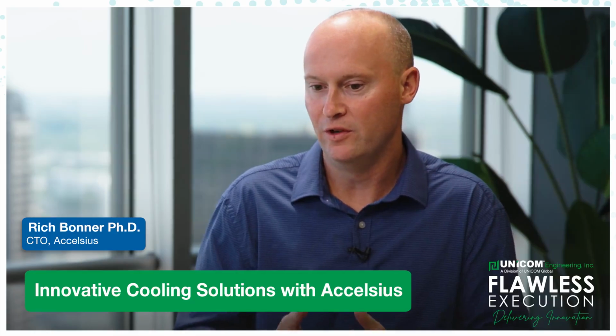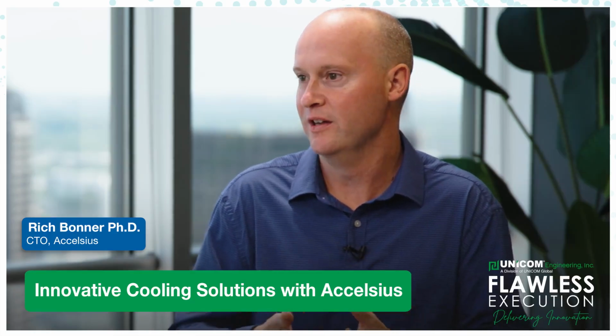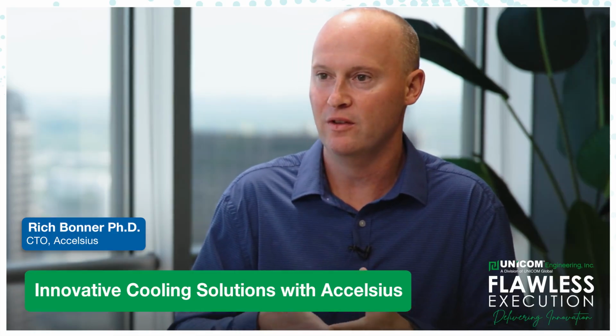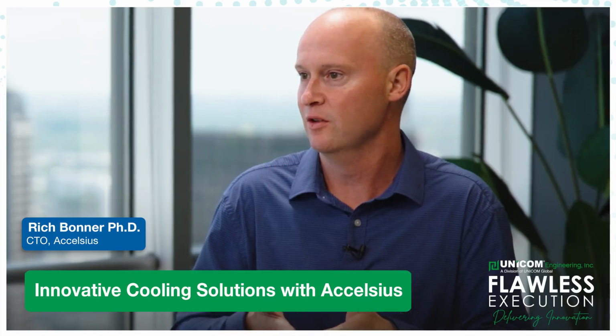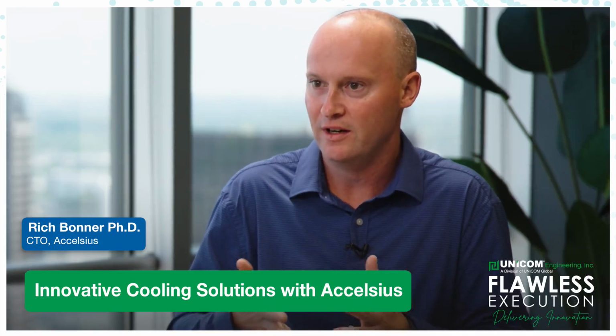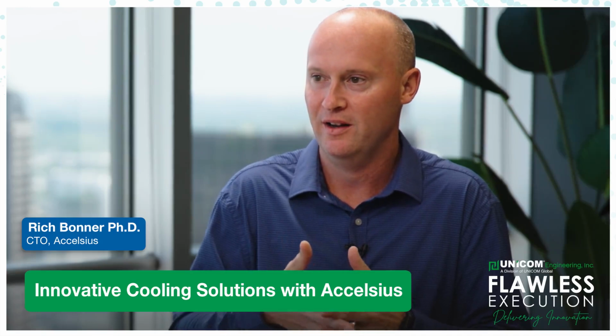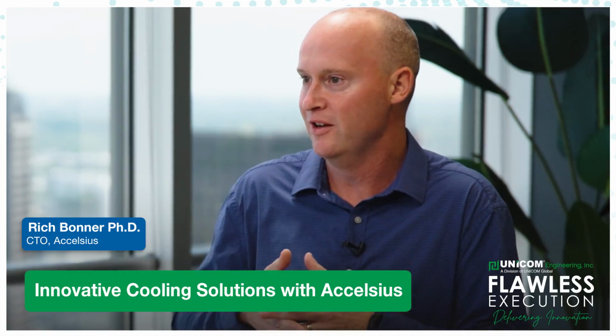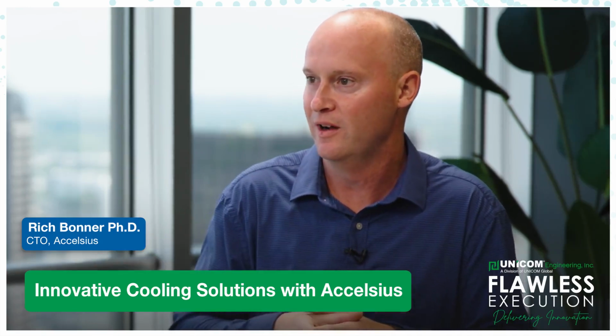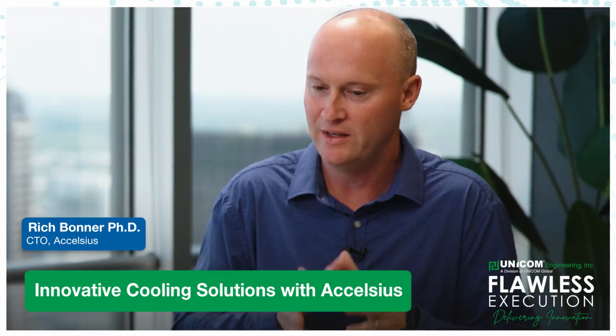I know there are a lot of refrigerants out there that you can use, so which one do you use? Which one do you find is the best? So we tend to focus on refrigerants that are so-called fourth generation refrigerants. The reason we focus on those families is that their GWP, global warming potential, is close to 1. So if you use a refrigerant with a GWP of 1, you get all the environmental, energy savings, and water savings benefits as well. Really, we think that's a win-win-win, so we tend to stick to those most modern forms of refrigerant.